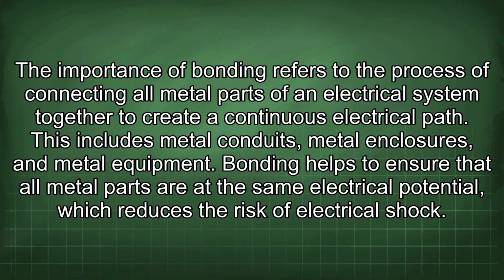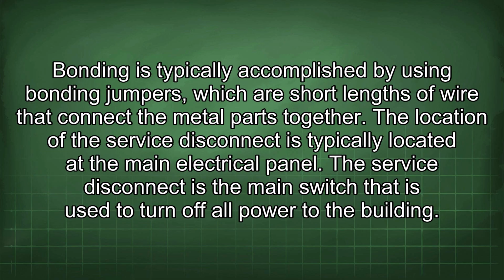The importance of bonding refers to the process of connecting all metal parts of an electrical system together to create a continuous electrical path. This includes metal conduits, metal enclosures, and metal equipment. Bonding helps to ensure that all metal parts are at the same electrical potential, which reduces the risk of electrical shock. Bonding is typically accomplished by using bonding jumpers, which are short lengths of wire that connect the metal parts together.